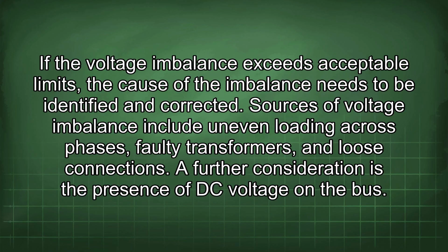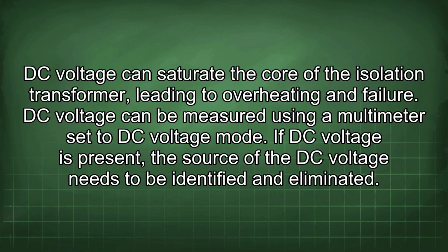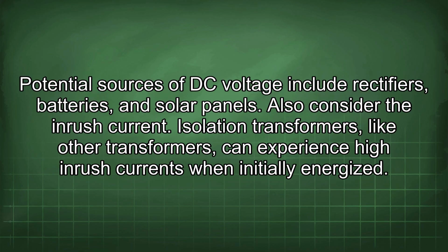A further consideration is the presence of DC voltage on the bus. DC voltage can saturate the core of the isolation transformer, leading to overheating and failure. DC voltage can be measured using a multimeter set to DC voltage mode. If DC voltage is present, the source of the DC voltage needs to be identified and eliminated. Potential sources of DC voltage include rectifiers, batteries, and solar panels.